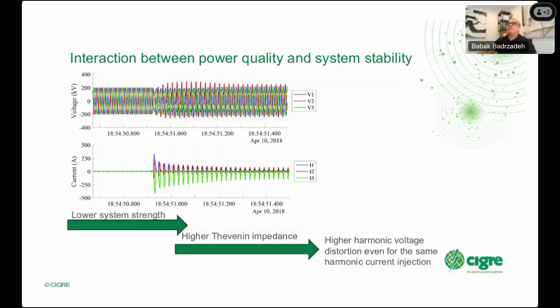This is an example of harmonic resonance in a very low system strength condition, meaning high impedance. If you inject even a small current, that would be sufficient to create a relatively high voltage, because there is a large impedance. Large impedance multiplied by a small current gives you a large voltage. A large voltage would result in the plant tripping because of the protection settings, and the same could apply and will apply in broader systems.